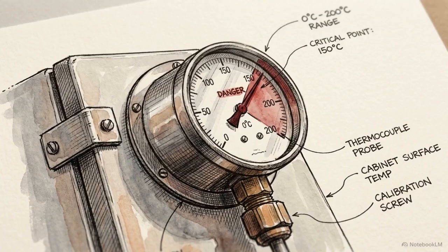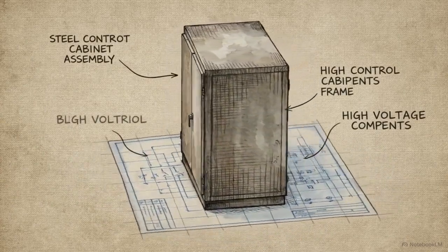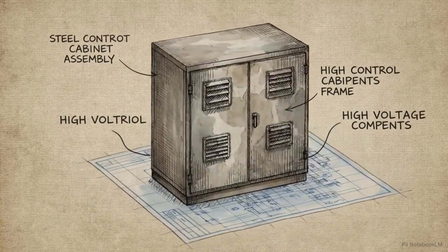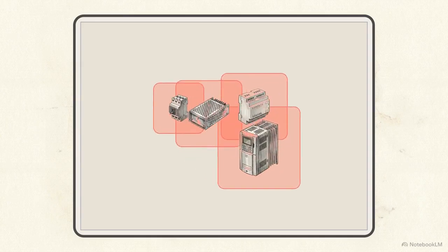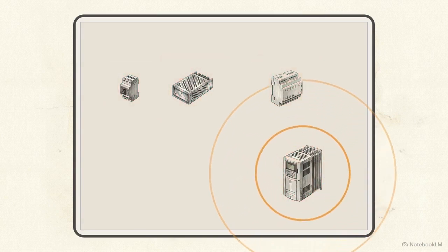Thermal limits. Custom control panel design requires a rigorous engineering process to translate an abstract schematic into a guaranteed, survivable physical architecture. The first constraint is translating the wiring diagram into a spatial layout inside a physical enclosure. Components are not placed randomly. Their arrangement is dictated by minimum clearance distances between live electrical parts and the specific thermal dissipation requirements of each individual device.